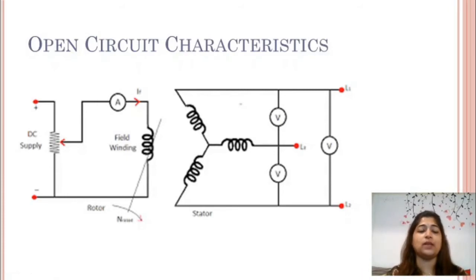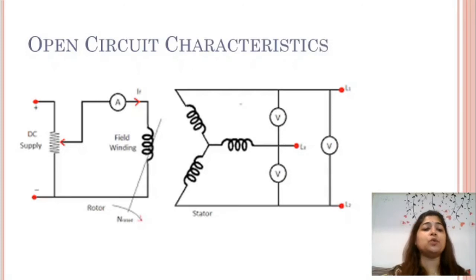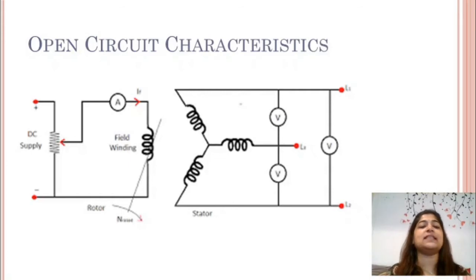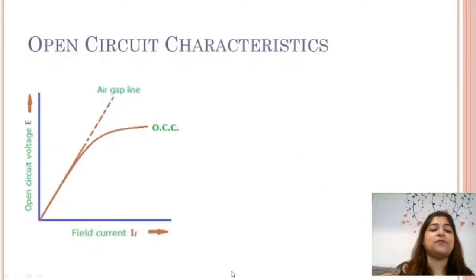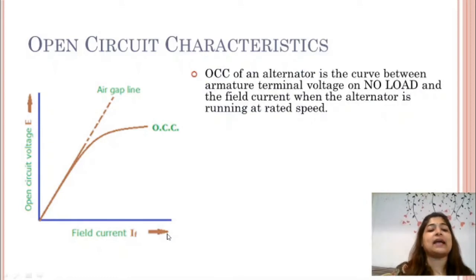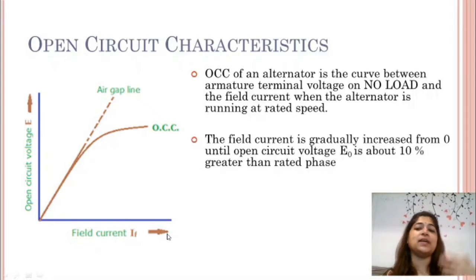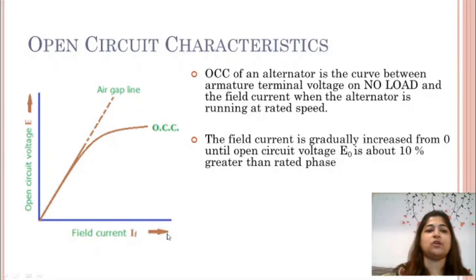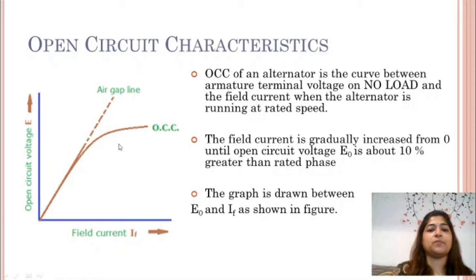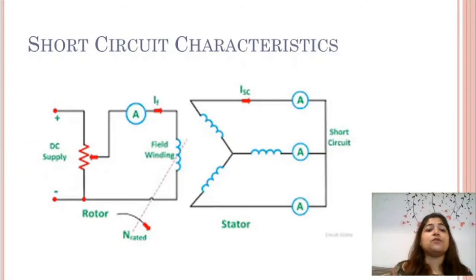When you give excitation to the field winding slowly and increase the current in the field winding, the voltage builds up across the armature winding. You note down this increment in voltage with the increase in current, take five to six readings, and then plot a graph. When you plot a graph between field current IF and open circuit voltage, the characteristic you get is called OCC — open circuit characteristics. The field current is gradually increased from zero until you get the open circuit voltage graph between E0 and IF.